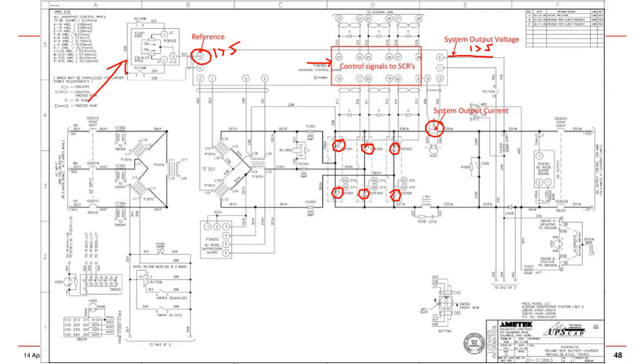So let's see what happens. Say our input went low, down to about 450 volts like in our example. Then the DC output is going to go low momentarily. This feedback cable goes up here, and the sensing voltage says the output's gone low. So the control board says it needs to send the gate signal earlier to increase the average voltage until we come back into equilibrium.